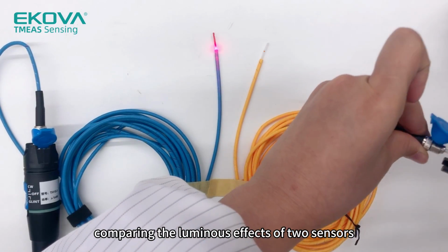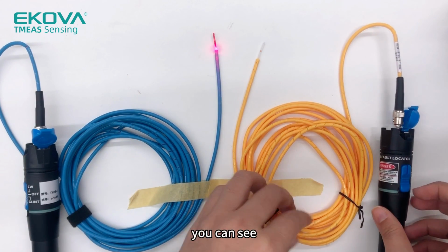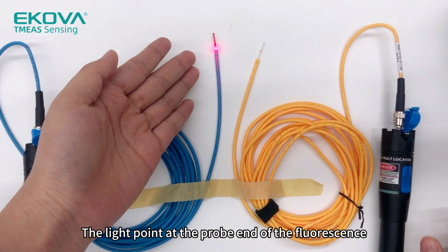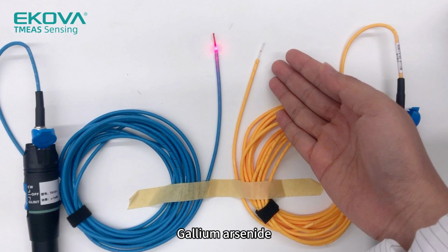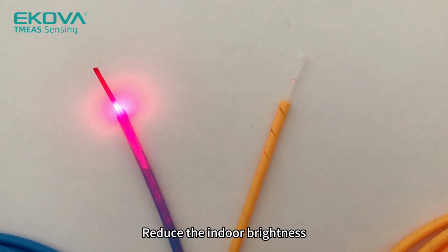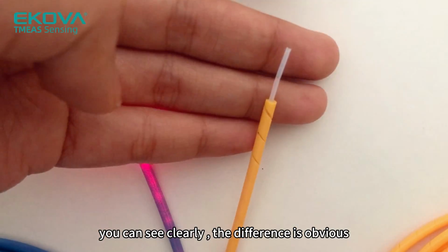Comparing the luminous effects of the two sensors simultaneously, you can see the light point at the probe end of the fluorescent sensor is relatively large. The gallium arsenide sensor tip light spot is relatively small, so look carefully. Reduce the indoor brightness and you can see clearly the difference is obvious.